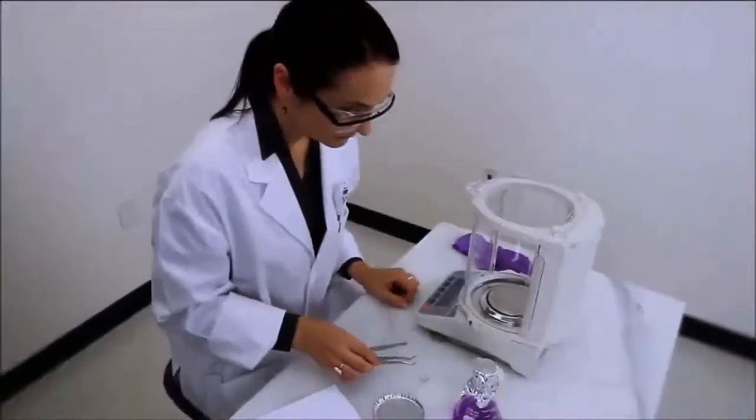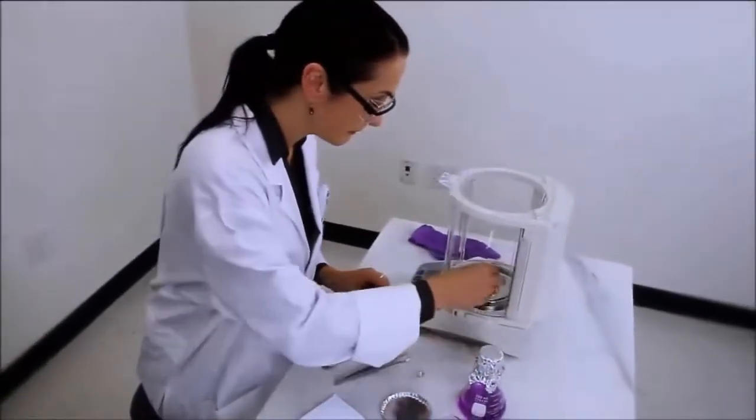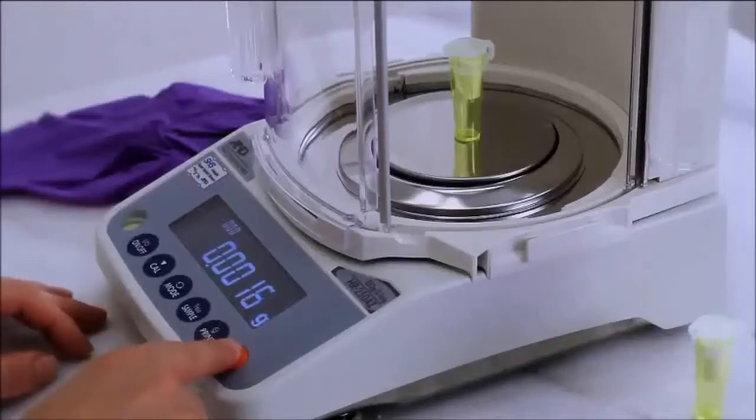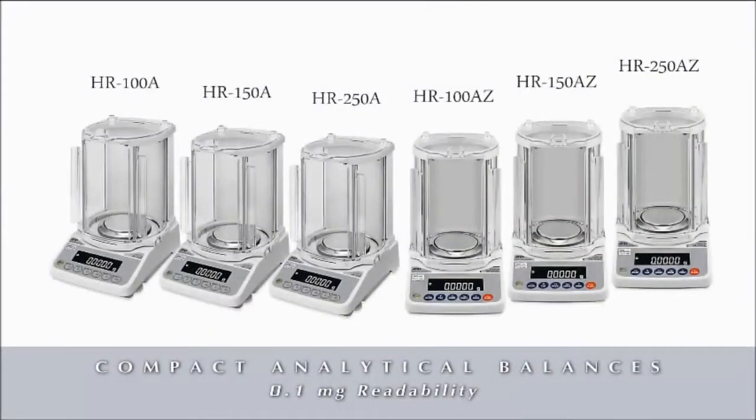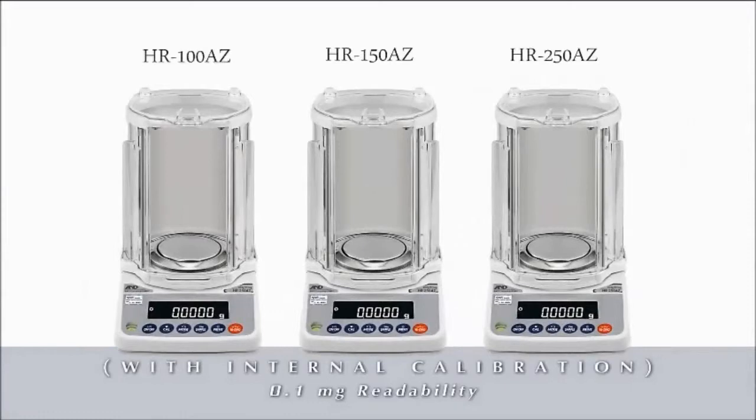Every lab needs a reliable balance. That's why you should get to know the new HR-A series of compact analytical balances from A&D. Six models are available in three capacities, all with 0.1 milligram readability. The HR-AZ models include internal calibration.